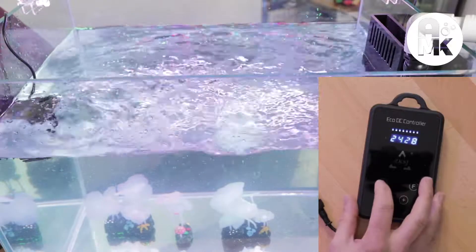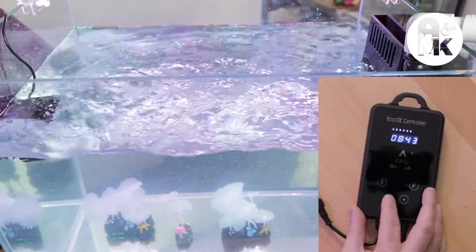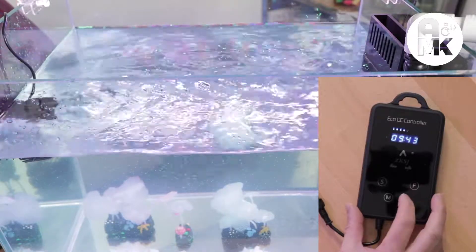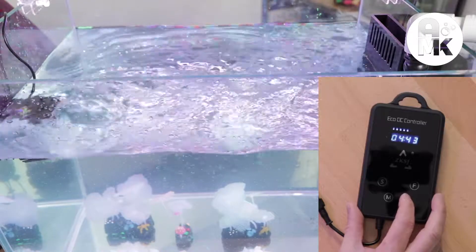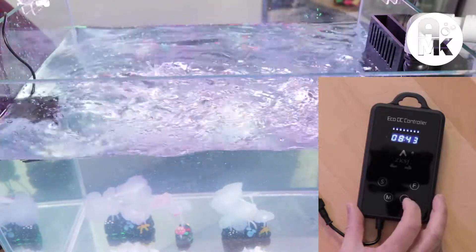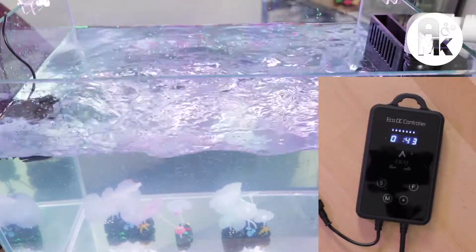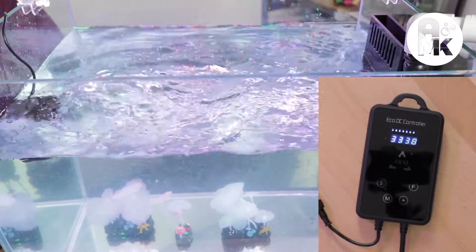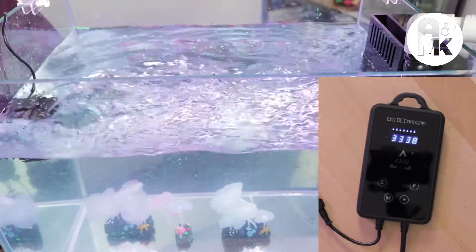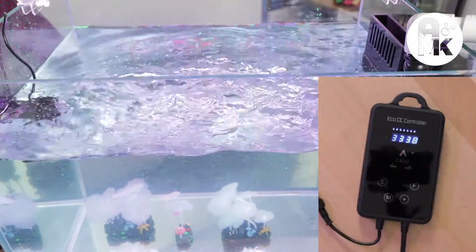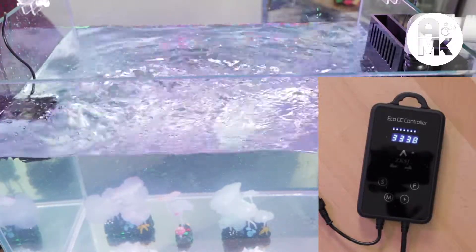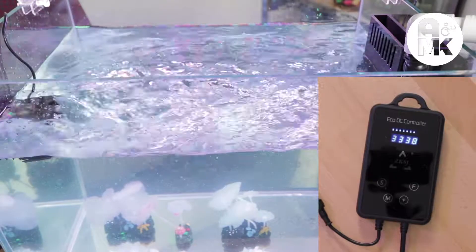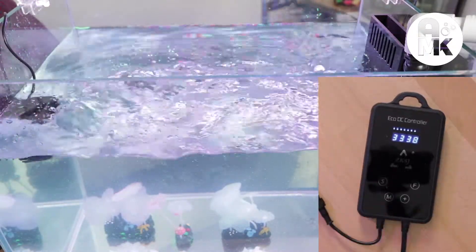Now we're going to set the clock again. And we're going to take this up now to daytime. So we're going to take this all the way up to nine. So nine o'clock in the morning, our day cycle is from nine to two o'clock. And we're going to let the pump kick from there. So here's the setting. So from nine to two o'clock, we're going to be at 3338. So three lets you know it's the third position or daylight. Three means it's going up to 80%. Three means it's in the constant stream mode. So we're going to have 80% of our flow. And in the constant mode, the last digit, which says eight doesn't really matter because it's constant. So there's no frequency changing up or down. So we're constantly at 80% flow. And that's what the pump is doing.